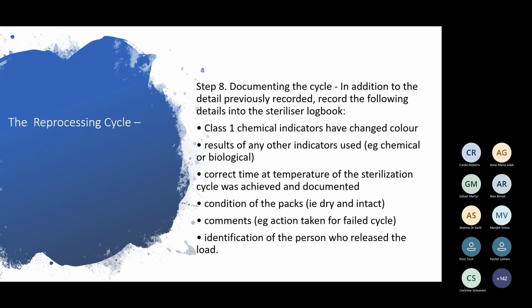So then, documenting the cycle. In addition to the details previously recorded, now you're going to record that the class 1 chemical indicators in your packs have changed color, so we know that they've been affected by steam. Results of any other indicators, whether you've got a class 4, 5, or 6 indicator in your machine. Correct time at temperature of the sterilization cycle was achieved, so we may look at the printout, or we may be looking at the information on the screen of the machine. Conditions of the pack, whether they're dry and intact, any other comments if you've failed the cycle, and the identification of the person who released the load.